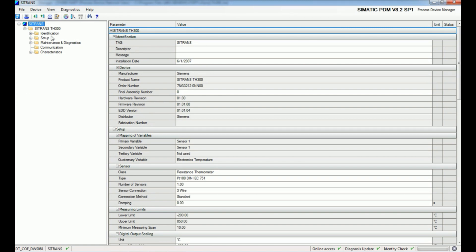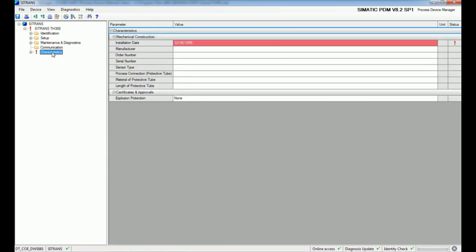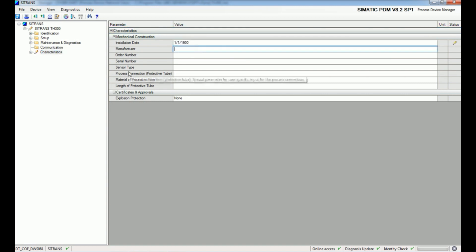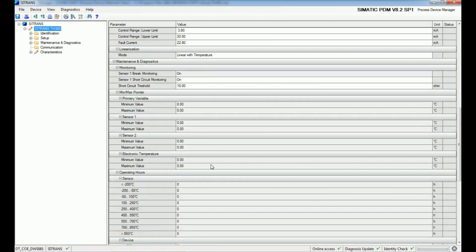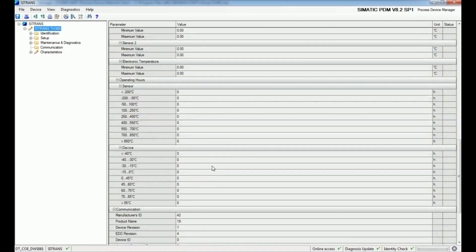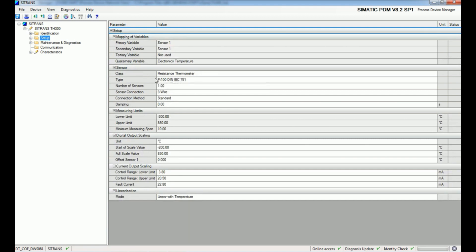The Process Device Manager gives us the parameterization options. Here we get identification, setup, maintenance, diagnosis, communication, and characteristics. We will rectify any errors and then upload the data from the HART modem. Using the upload option, whatever parameters are stored in the temperature controller will be loaded to the PC. After changing parameters we can download the parameterization back into the TH300 temperature controller.